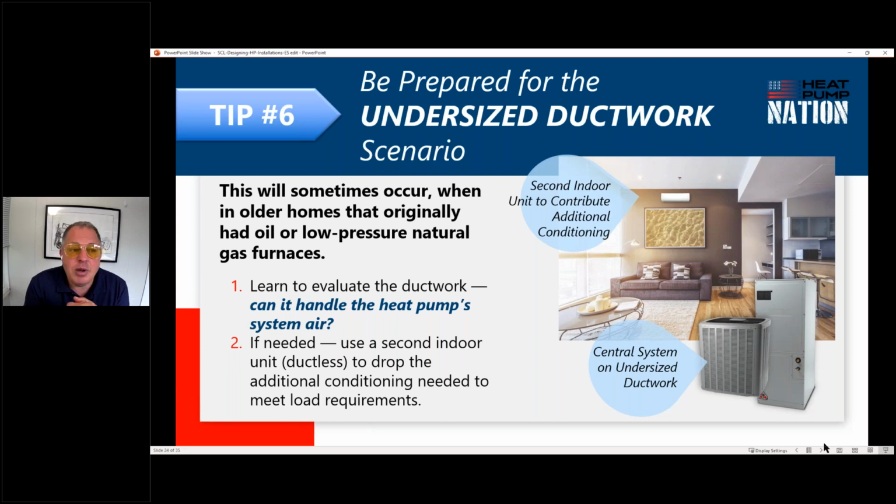Okay, it's not impossible. What you can do, and each of the best manufacturers I know, like Daikin, Mitsubishi, Carrier, Fujitsu, all the main variable capacity heat pump manufacturers, make a heat pump that has a furnace replacement for the central ductwork, and then that same heat pump can put 1 or 2 or so, even more possibly, but I would recommend keep it simple, 1 or 2 wall-mounted ductless units elsewhere in the home.